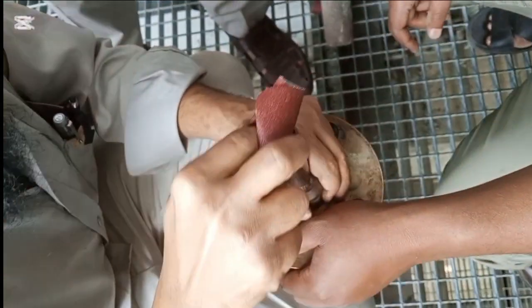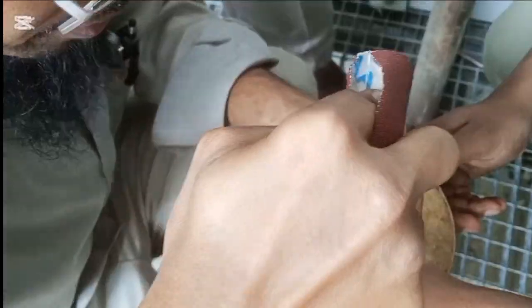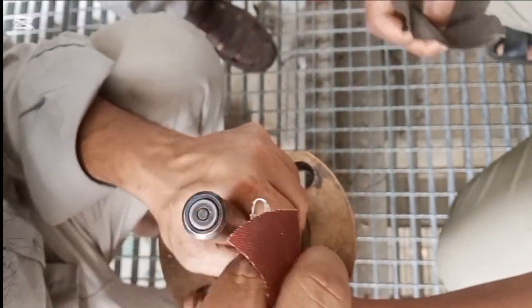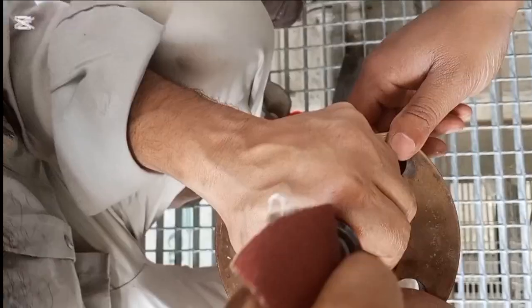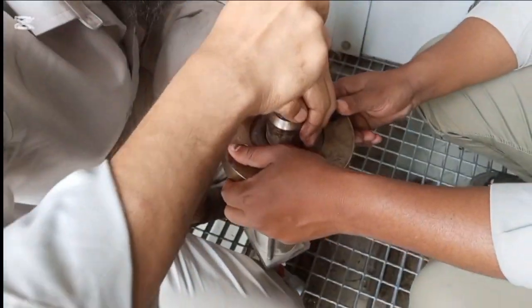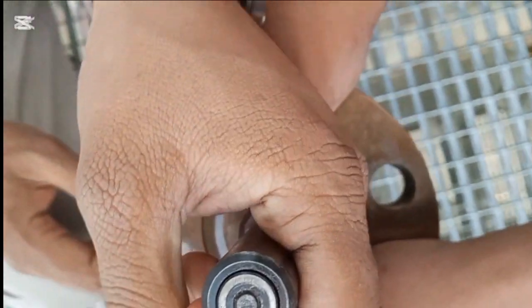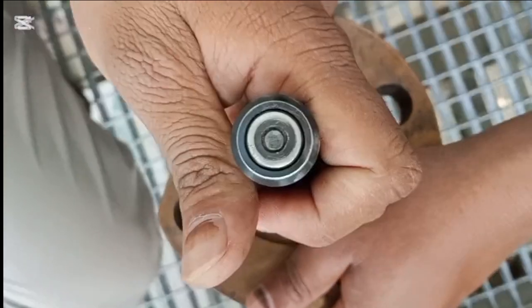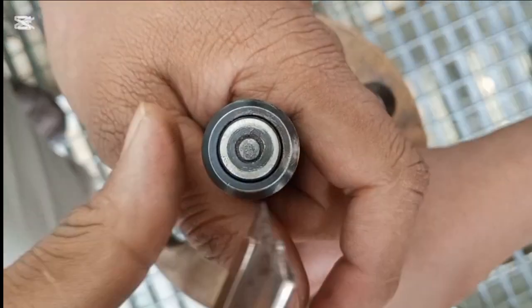Over the electrode there is a porcelain insulator. On the outer side of the electrode we saw some dust particles, and we cleaned them with thin emery paper. The spark plug is connected to the fire line, so at the ignition period a spark occurs. But when the flame is okay and firing is completed, the spark plug has no function, yet it always stands in a high temperature stage. So here is some dust particle.